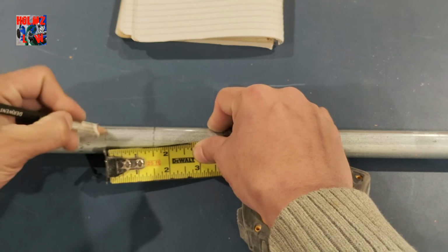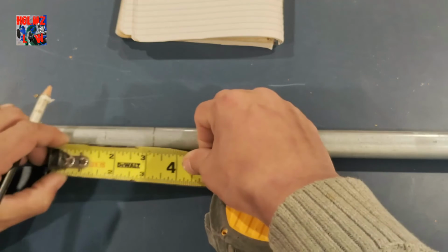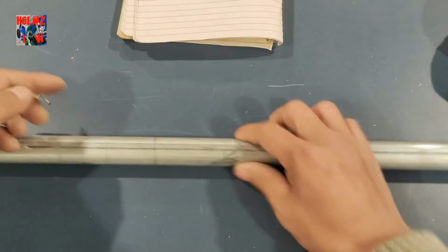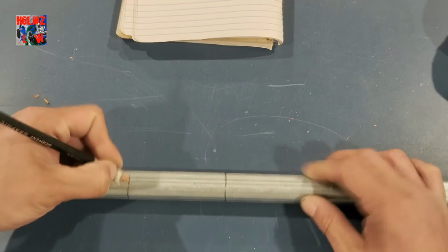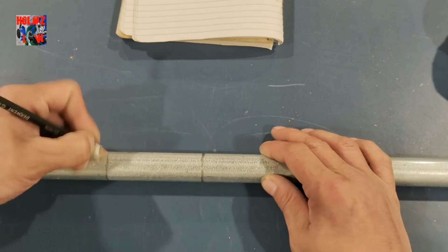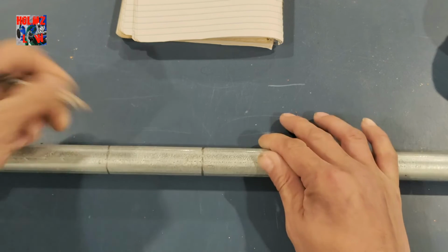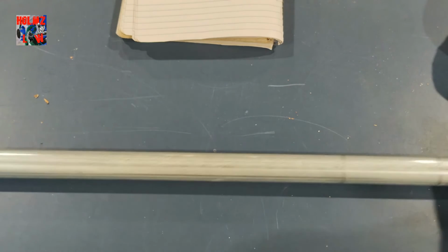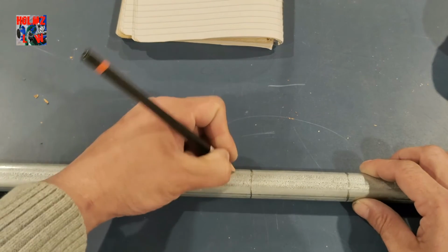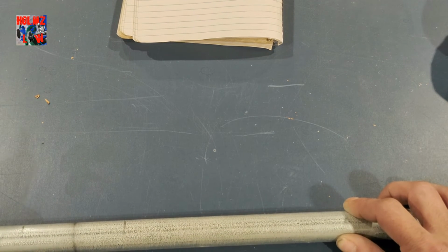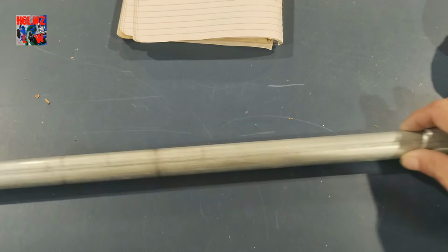This is where the start of my bend is, plus my other 1.5 inches for my front of hook. So my bend will be here, and this is my center of my bend, but this is where I'm going to place my actual bender and bend. So when I'm done bending, this should be the center of my bend. Great. Now I like to put a mark here as B. This way we know that's where I'm going to place my bender, and A. There you go.